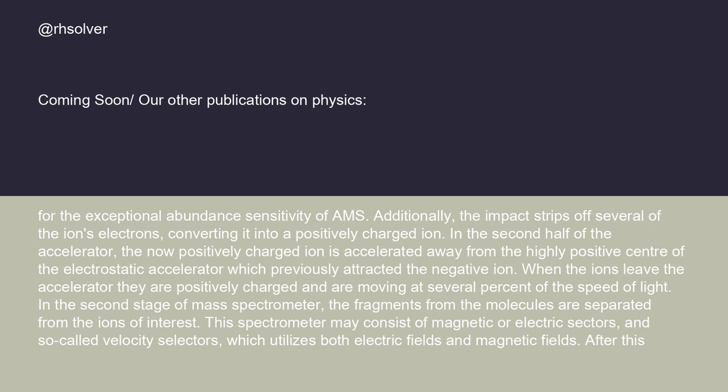In the second half of the accelerator, the now positively charged ion is accelerated away from the highly positive center of the electrostatic accelerator, which previously attracted the negative ion. When the ions leave the accelerator, they are positively charged and moving at several percent of the speed of light. In the second stage of mass spectrometer, the fragments from the molecules are separated from the ions of interest. This spectrometer may consist of magnetic or electric sectors and so-called velocity selectors, which utilize both electric fields and magnetic fields.